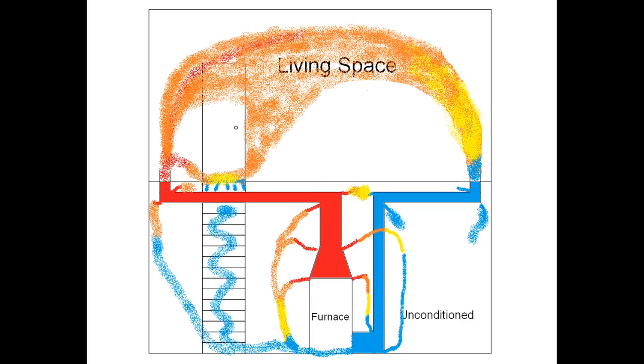So if air is leaking in the returns, whatever gets sucked out of the basement is not getting sucked out of the living space. So that air has to have some source, and the common sources are open stairwells, and even stairwells with doors, because a door on a stairwell is unsealed, right? It's an interior door, so it doesn't need to be sealed. But if the ductwork in the basement is leaking, it creates a small negative pressure which sucks that cold air off the floor, down the stairwell, into the furnace to be circulated, and it never quite makes it across the whole room to the return air grill. So leakage is a huge problem in most systems. It results in uncomfortable rooms and high heating costs.